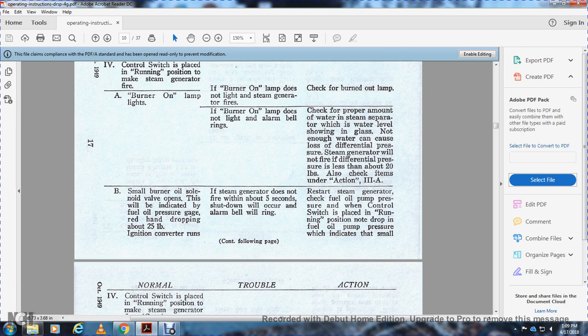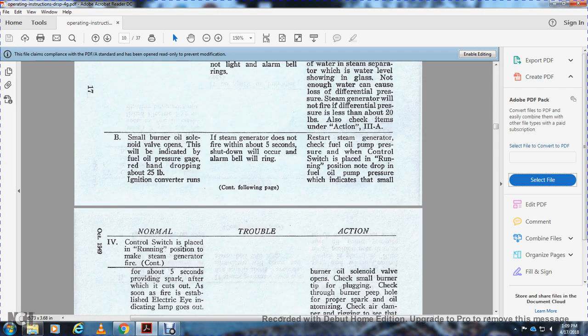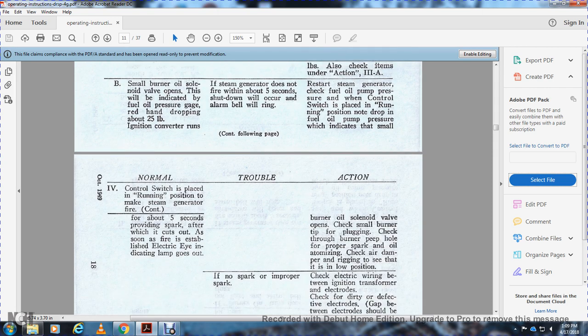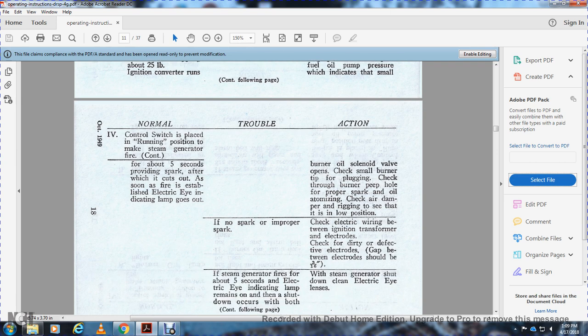Restart the steam generator. Check the fuel oil pressure pump when the control switch is placed in the running position. Note the drop of the fuel oil pump pressure, which indicates the small burner oil solenoid valve opens. Check the small burner tip for plugging. Check through the burner peephole for proper spark and oil atomizing. Check the air damper and linkage to see if it is in the low position. All right, the control switch is placed in the running position to make the steam generator fire.